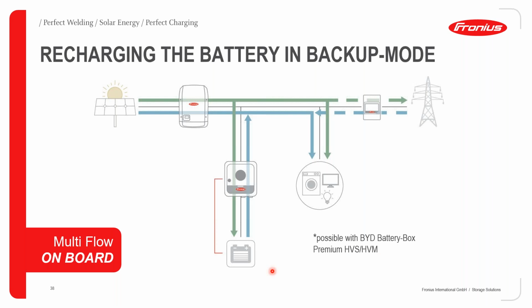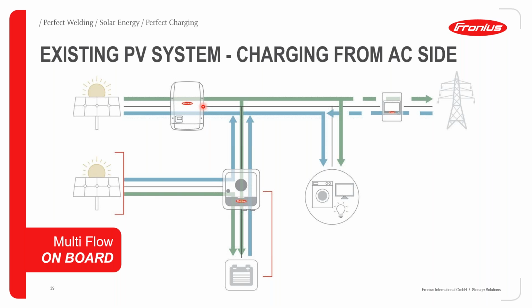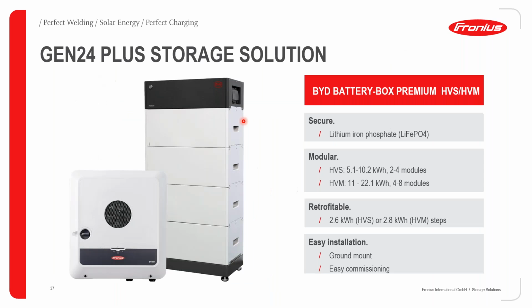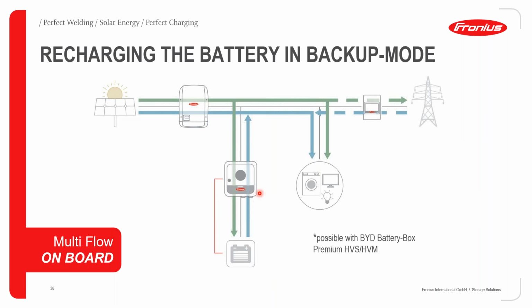So in terms of how the operation with the Gen 24 plus batteries can look, we can look at several scenarios that emphasize the multi-flow technology included in the Gen 24 inverters. In this particular setup, we can see an example of battery charging in backup mode. And also, we can do charging when the Gen 24 inverter has its own array of PV connection. So this particular example indicates how you can retrofit the Gen 24 Plus inverter into an existing grid-tied installation.